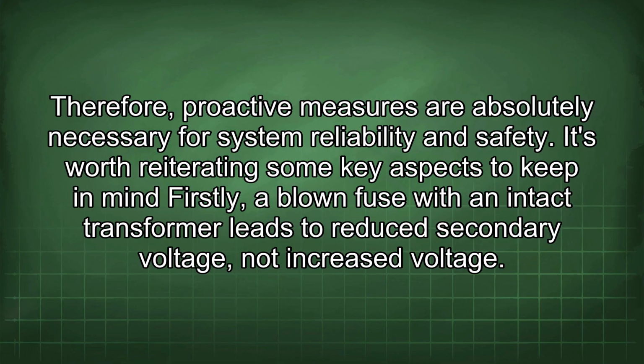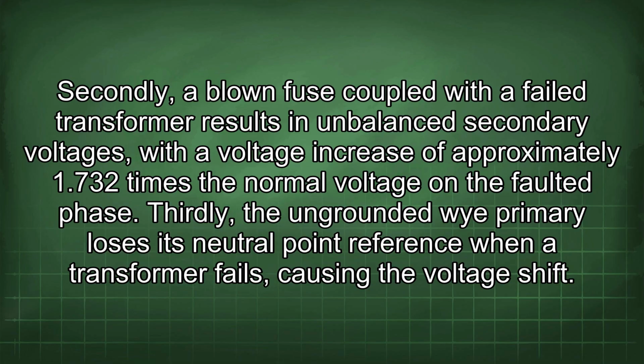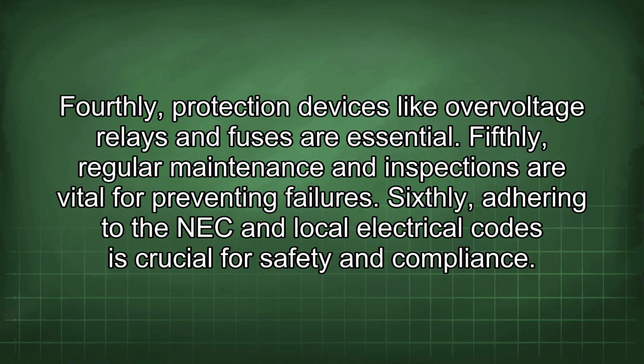It's worth reiterating some key aspects to keep in mind. Firstly, a blown fuse with an intact transformer leads to reduced secondary voltage, not increased voltage. Secondly, a blown fuse coupled with a failed transformer results in unbalanced secondary voltages, with a voltage increase of approximately 1.732 times the normal voltage on the faulted phase. Thirdly, the ungrounded Wye primary loses its neutral point reference when a transformer fails, causing the voltage shift. Fourthly, protection devices like overvoltage relays and fuses are essential. Fifthly, regular maintenance and inspections are vital for preventing failures.